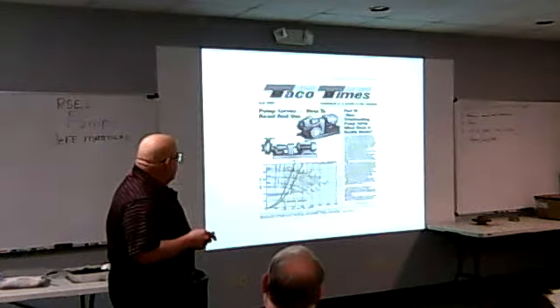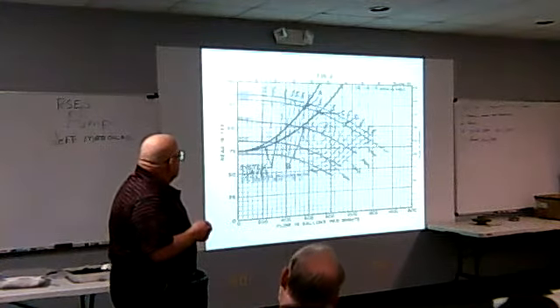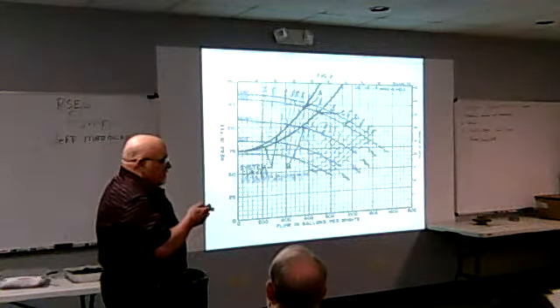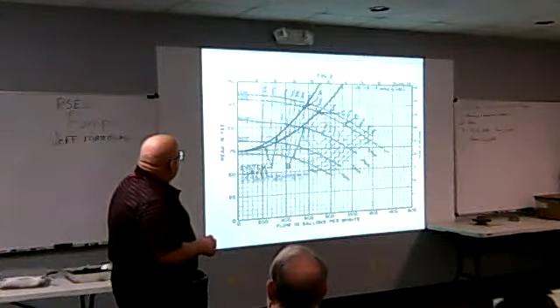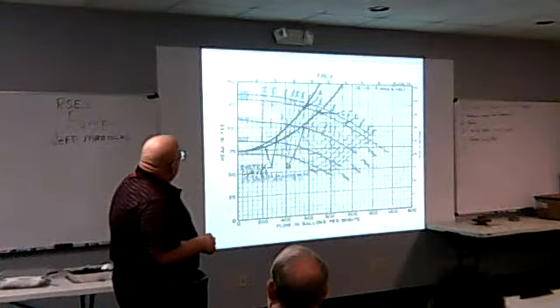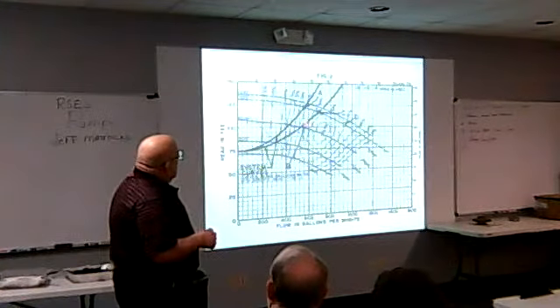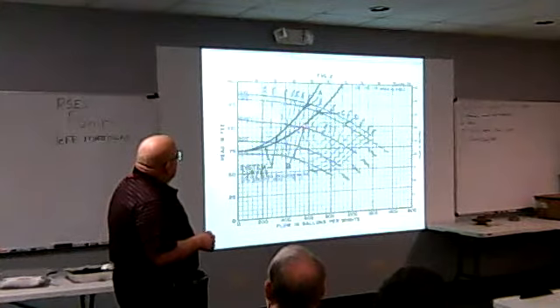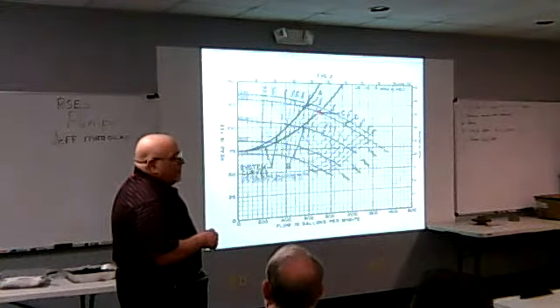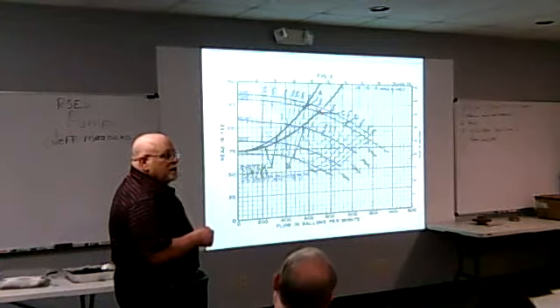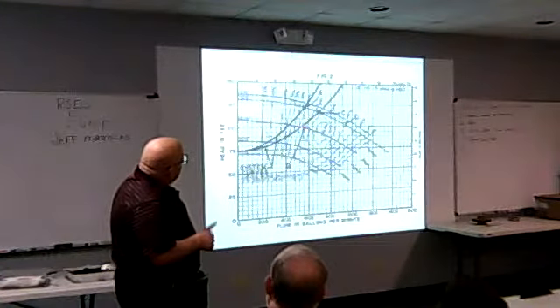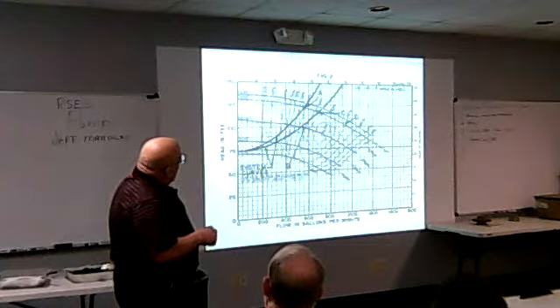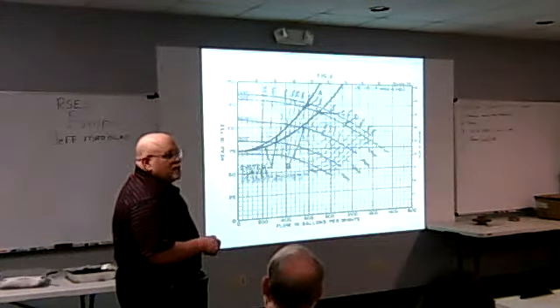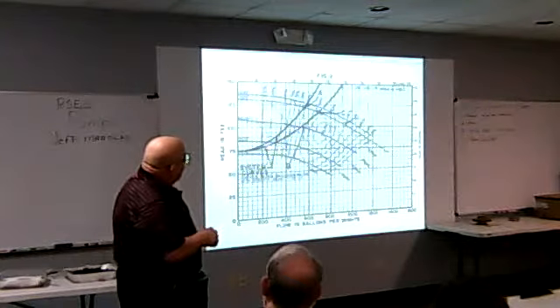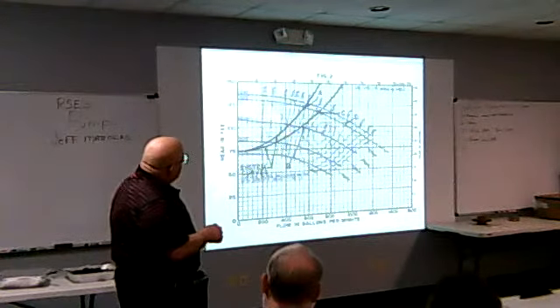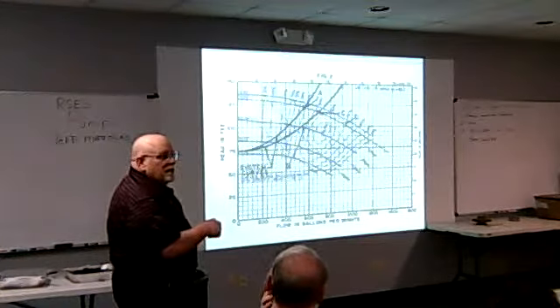Non-overloading and overloading. This is very important. Okay, a better curve I do here. A lot of people assume this is, let's say this is our operating point. When you lay in the curve, if this is the true operating point, if I have an 11-inch impeller, the pump's not going to operate here. It's actually operating here because of my larger impeller. If I designed and I missed my design that much, I'm still going to pull this much horsepower, at least 25 horse per run, because the pump has to be on the system curve. The system's only seeing this, but I'm actually on the curve here.